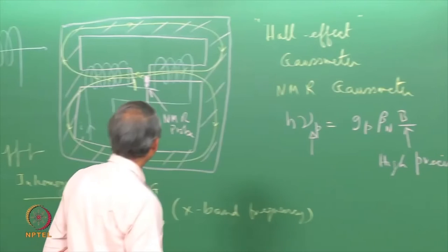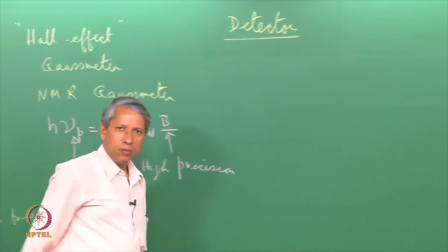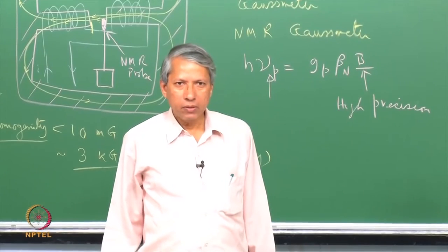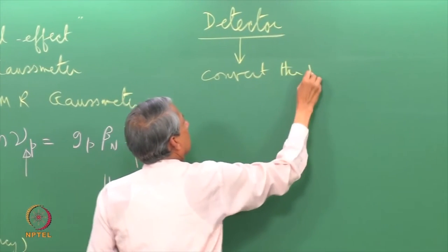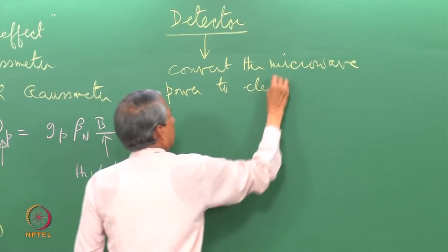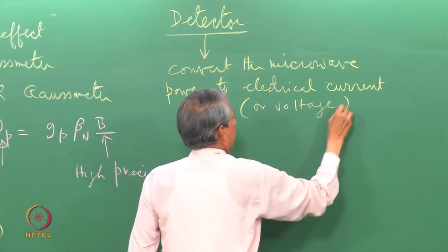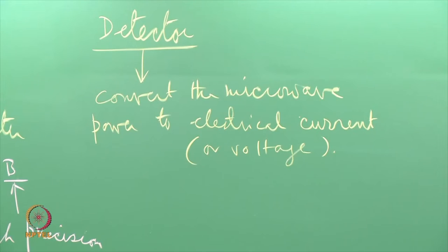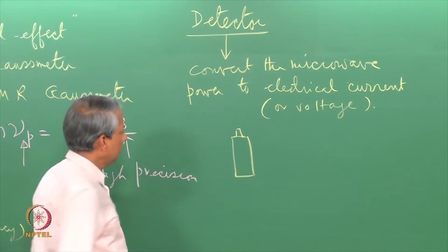The next important component of the spectrometer is of course the detector. The detector's job is to measure the microwave power that is coming out of the cavity and which will carry the information about the absorption of microwave by the sample. What it does is to convert the microwave power to electrical current or voltages so that it can be further amplified and recorded. The detector that is used in EPR spectroscopy is usually a silicon diode. The diode is kept inside.